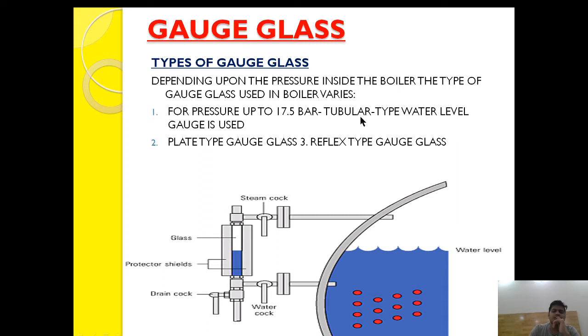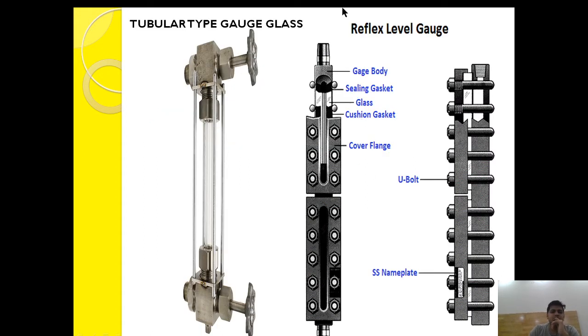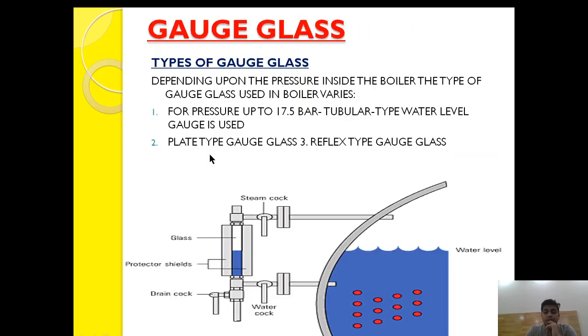The tubular type gauge glass is very simple in construction. As you can see, this is the steam cock and this is the water cock, and both cocks are held by a tubular type gauge glass having a tube type structure which is mounted here. The design is very simple and hence it can be used up to a pressure of 17.5 bar. But for a higher pressure range we have to modify the design.